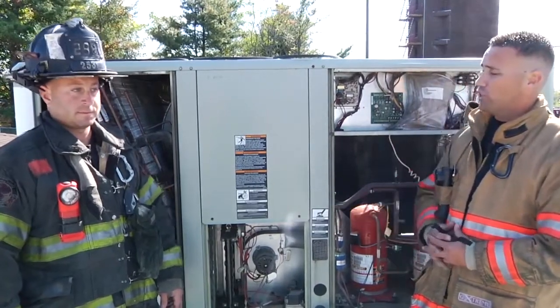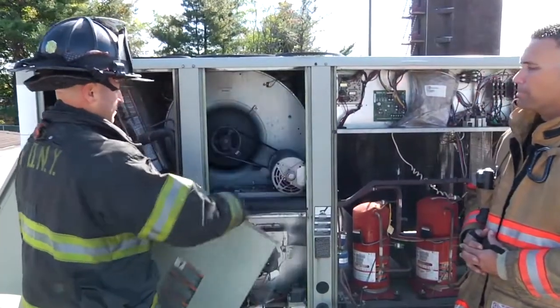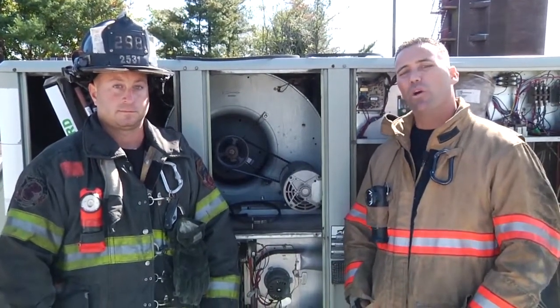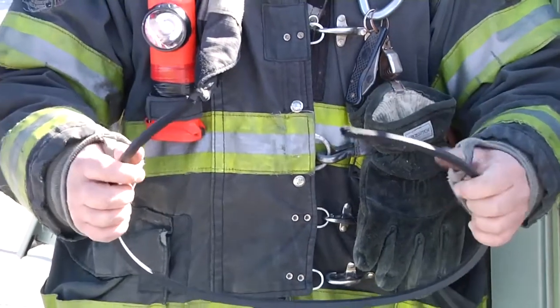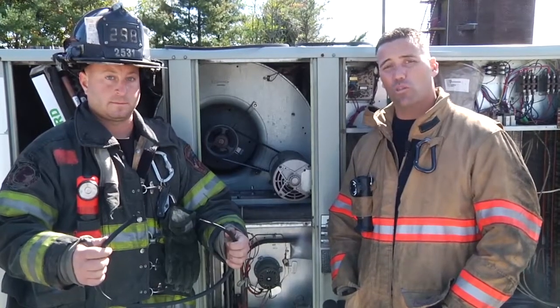So we're going to remove this service panel. Once we locate the sticker with the hand caught in the pulley and remove that service panel, we're going to look inside — and like this right here, we have a belt that's lying on the base of the compartment. This belt is obviously completely burnt out. We found the root cause of the odor and the smoke.